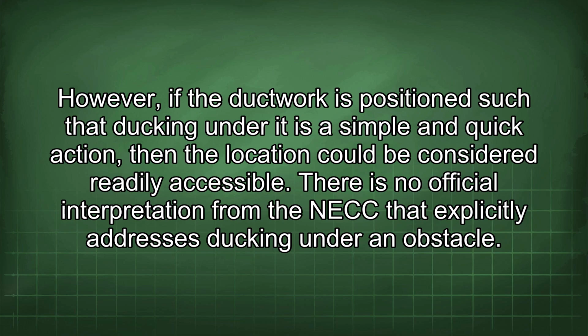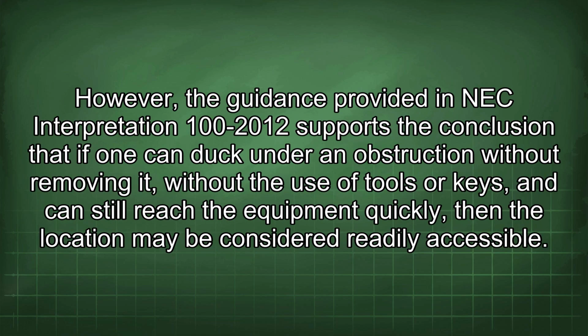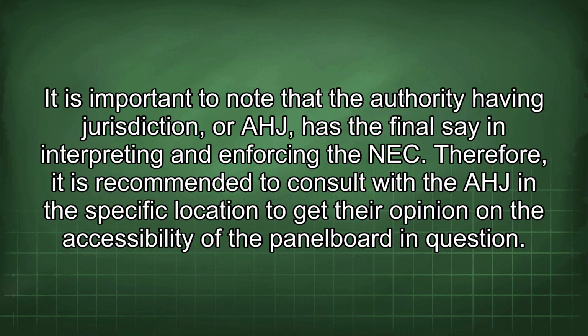There is no official interpretation from the NEC that explicitly addresses ducking under an obstacle. However, the guidance provided in NEC Interpretation 100-2012 supports the conclusion that if one can duck under an obstruction without removing it, without the use of tools or keys, and can still reach the equipment quickly, then the location may be considered readily accessible. It is important to note that the authority having jurisdiction, or AHJ, has the final say in interpreting and enforcing the NEC. Therefore, it is recommended to consult with the AHJ in the specific location to get their opinion on the accessibility of the panel board in question.